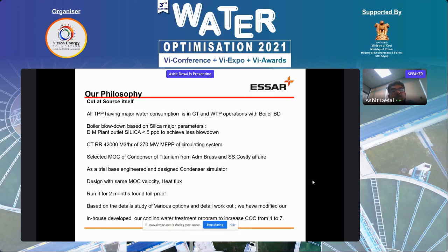Now, the second source, as I said, is the cooling tower, the major source of water consumption. We have a big cooling tower, 42,000 meter cube per hour of circulation rate for our 270 megawatt multi-fuel power plant. This shows our commitment towards water conservation. We have selected a titanium tube condenser, which is 4 to 10 times costlier than normal admiralty brass or stainless steel. It's a very costly affair, but keeping in mind that water needs to be conserved on priority, management has decided to go for the costly option.